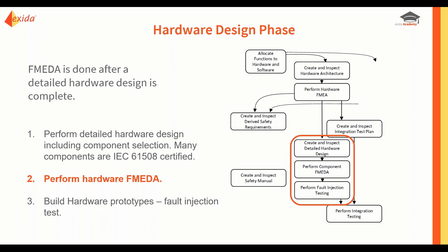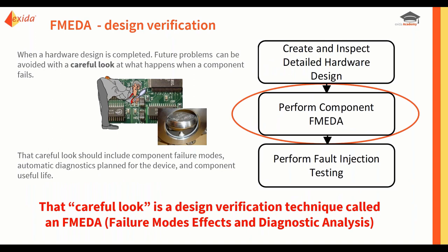So I suppose the key takeaway is, the sooner you do an FMEDA, and that's pretty much at the time when your hardware design is completed and your component selection is finalized, the better. That's the time to do an FMEDA, before any engineering time or money is wasted in actually physically building a prototype. The FMEDA allows you to look at the component failure modes and see what impact each component failure would have on the overall system design.